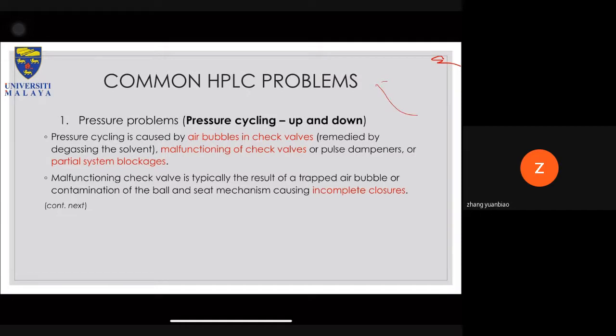Right. So what might also happen is that the pressure is cycling up and down, meaning it doesn't go down and stay down, it doesn't go high and stay high, it keeps on doing that, like a sinusoidal curve. Pressure cycling is normally caused by air bubbles in the check valve in the pump, remediated by degassing the solvent, malfunctioning of the check valve or pulse dampener, or partial system blockage. Additionally, if the pressure goes up and down, then definitely there's an air bubble somewhere in the system that keeps going up and down.